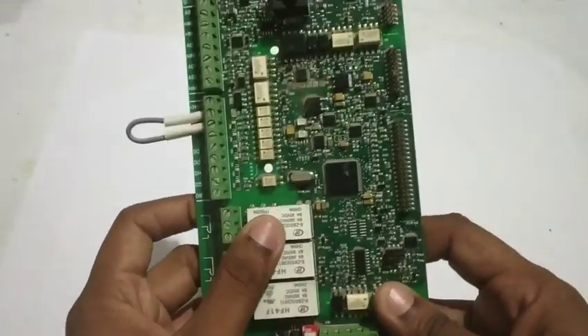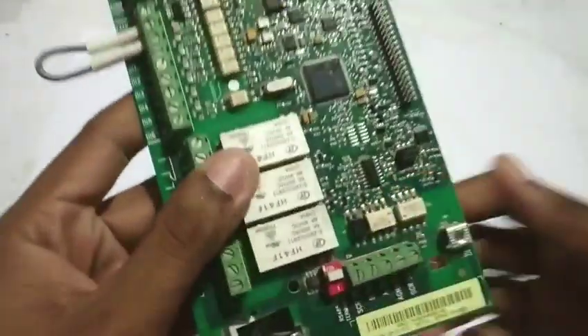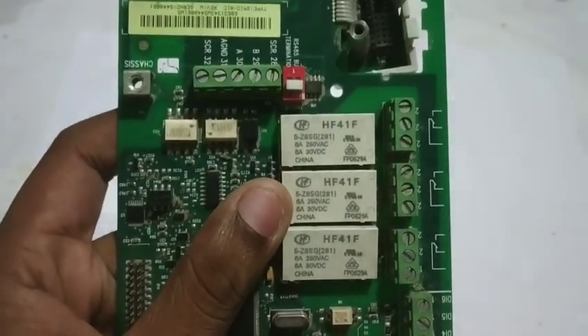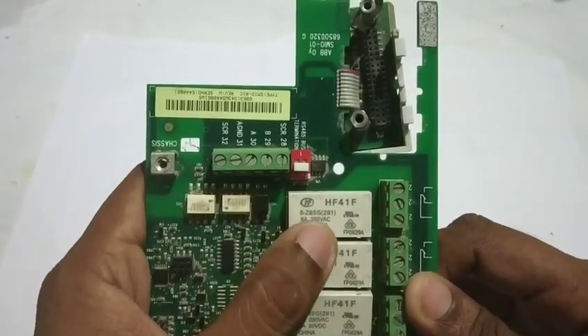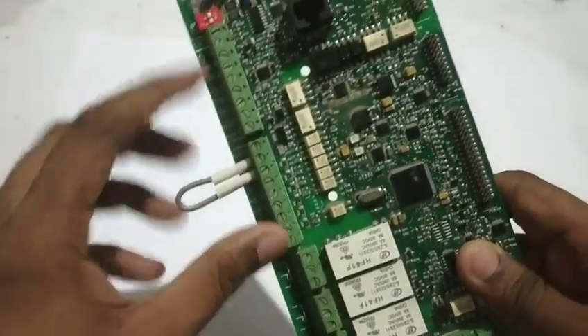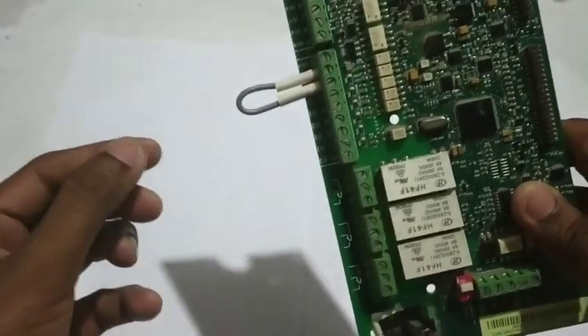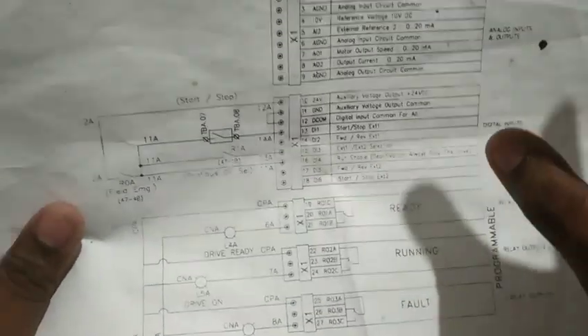Now let's look at the relay outputs — there will be 3 connectors. The relay rating is 250V single phase supply with 6 amps. These relays are programmable via parameters: you can set them for drive ready, running, or fault conditions.